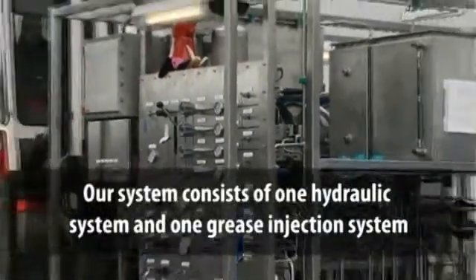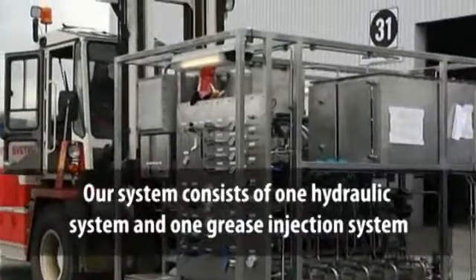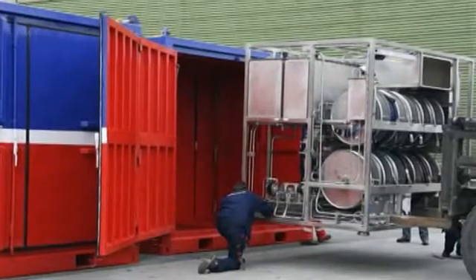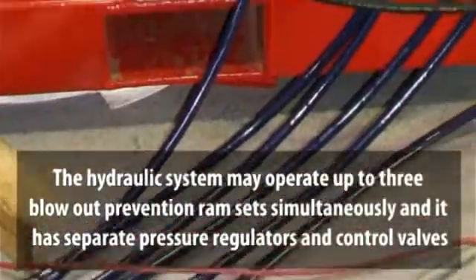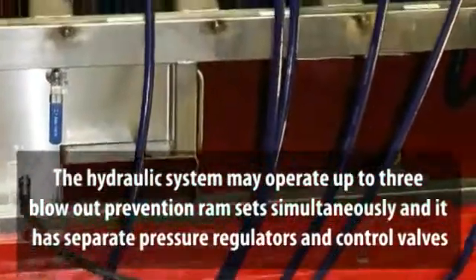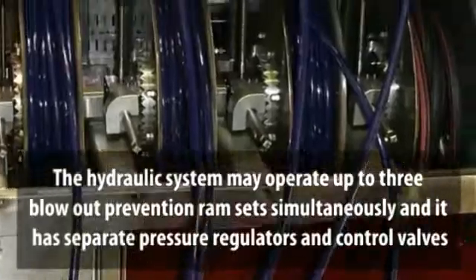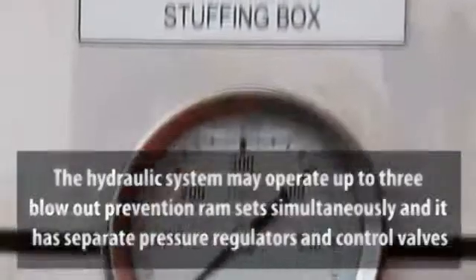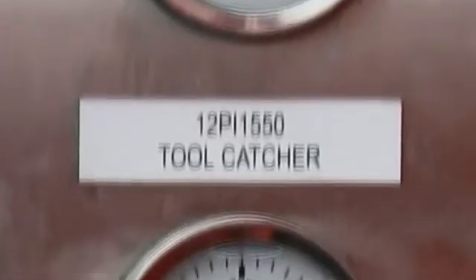The hydraulic control system controls blowout prevention ram sets, and the grease injection system seals the wire when the rams are closed. The hydraulic accumulator system may operate up to three blowout prevention ram sets simultaneously, and it has separate pressure regulators and control valves for controlling each ram set.